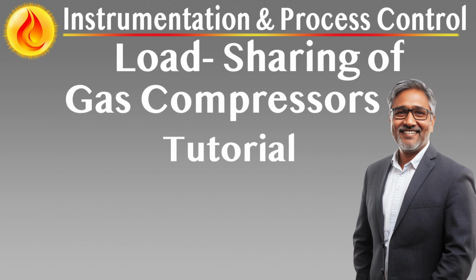Control actions and flow redistribution. Compressors operating closer to surge, more negative dev, are offloaded slightly to increase margin. Compressors with more positive surge margin are tasked with slightly higher throughput. This balancing is done continuously and smoothly, with control outputs biased accordingly. Recycle valves, speed set points, or guide vane positions are adjusted locally. No external operator intervention is required. Loop decoupling support. Balancing logic is supported by isolation between surge, speed, and recycle control loops. Prevents feedback cross-interference and allows each controller to act independently, yet harmoniously.